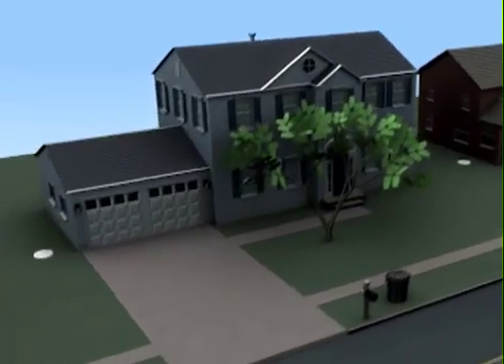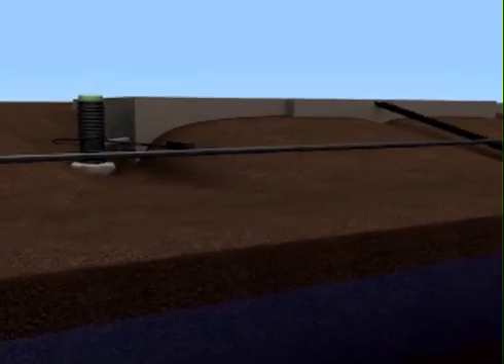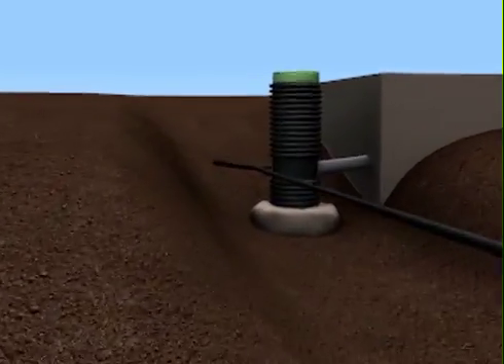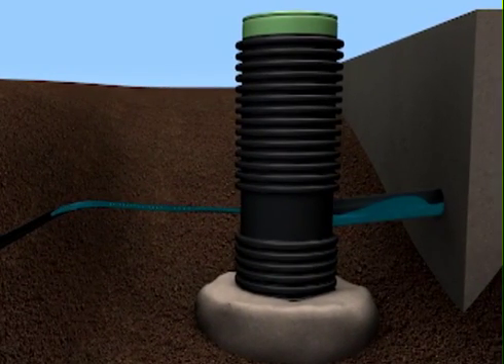The Riverview Landing project was unique in that we had to provide on-site sewage disposal — there were no public sewers available. The terrain was such that several lots were lower than the only site available for disposal. There was high bedrock in the area, and the lots were large, requiring extensive lengths of sewers to serve each lot. Those three factors combined to make a low-pressure sewer system the only economical and feasible solution, and in doing so we saved in excess of a hundred thousand dollars.